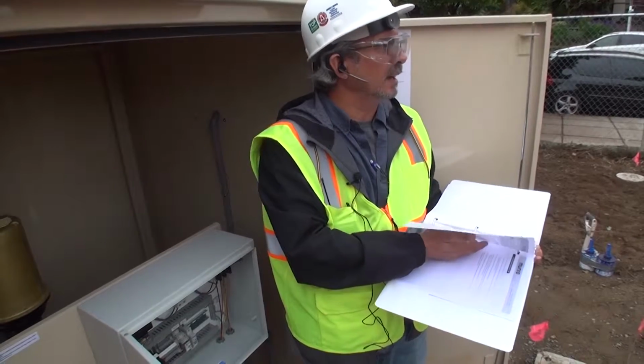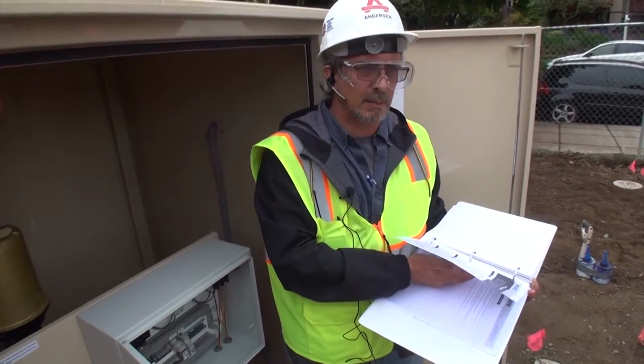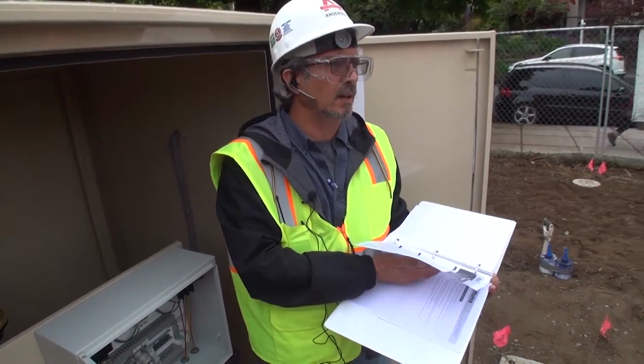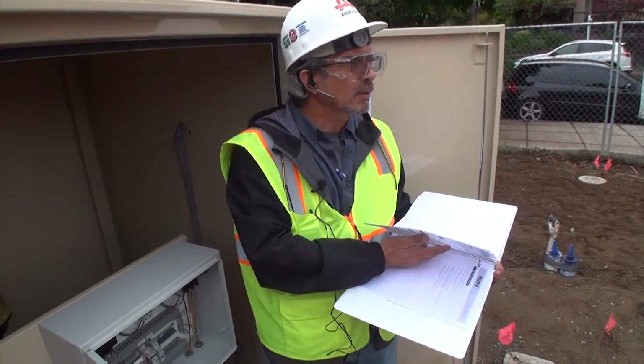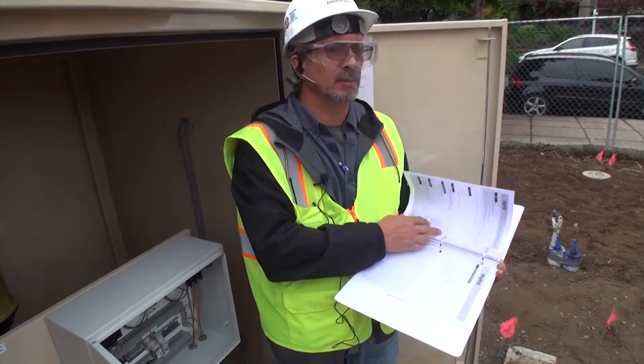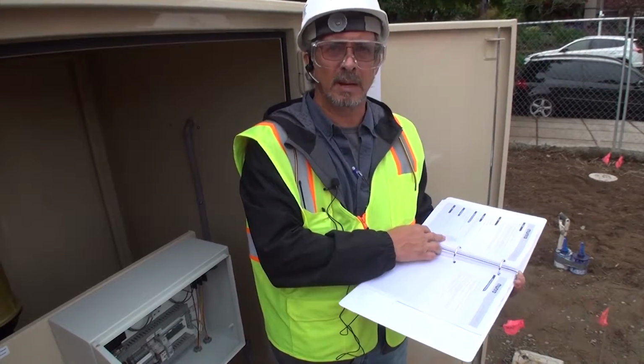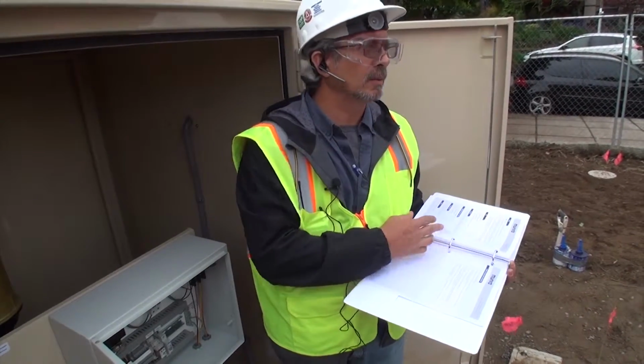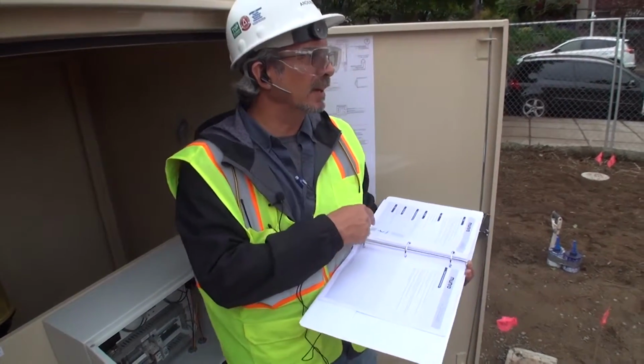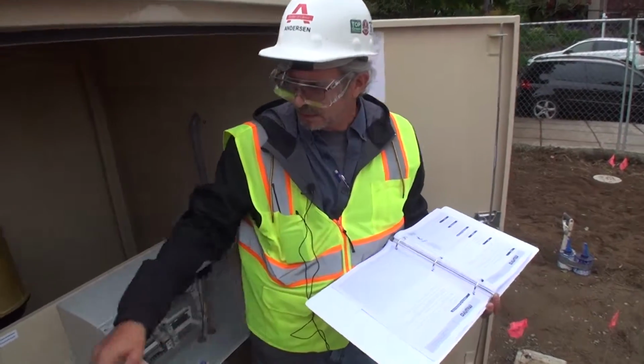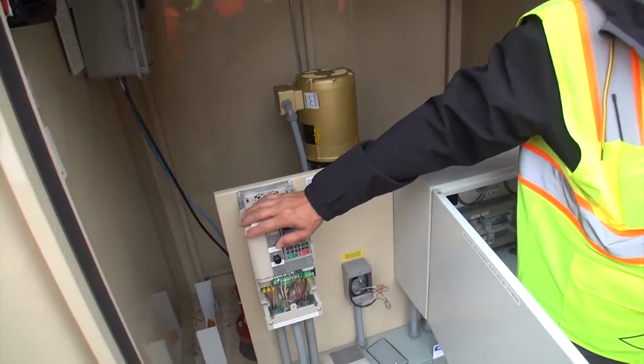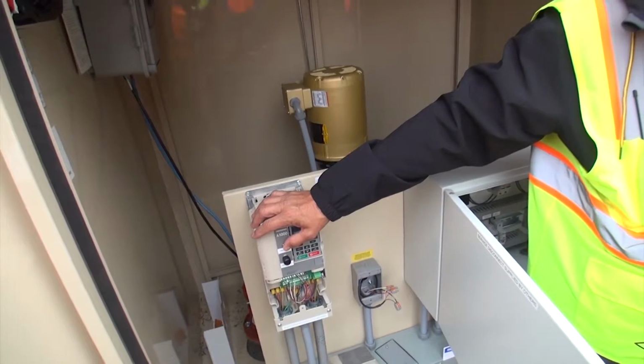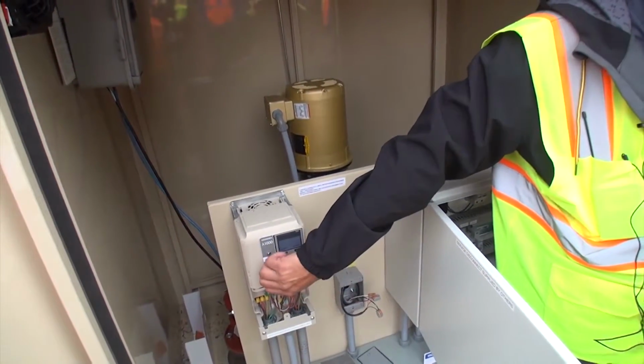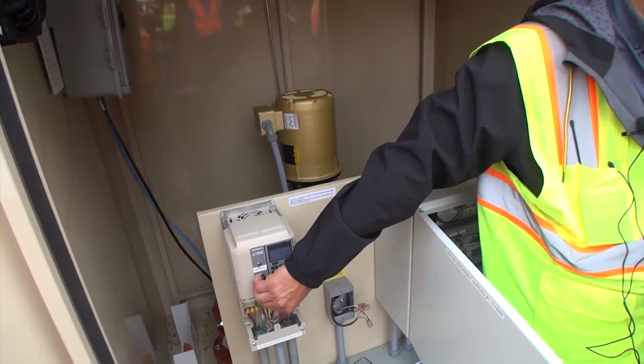I'm ashamed to tell you that I have done a PM on a pump station, walked away, and got a call from the customer after I was hours away and found out that the customer's complaining the station's not running. I went back to find out I forgot to put it back in auto. Seems like a silly thing, but we write it down just so you think about it before you leave. This is auto. That's off. That's hand. This is the speed control when it's in hand.